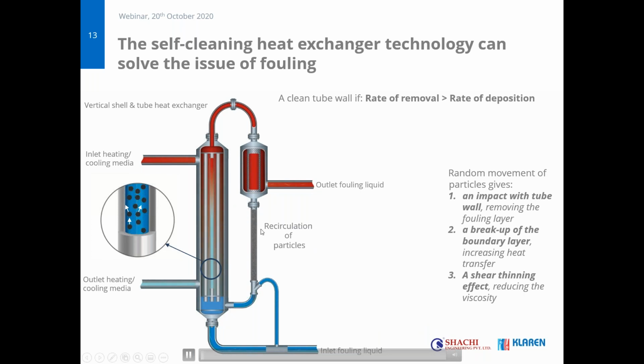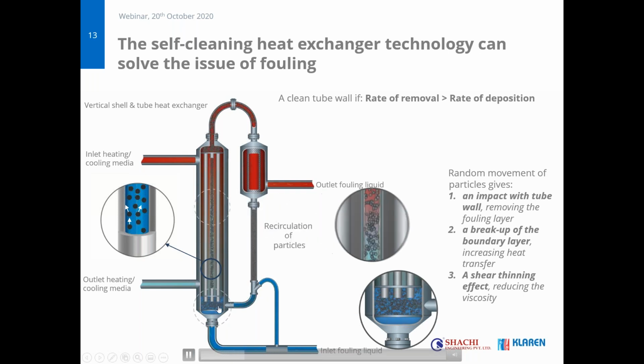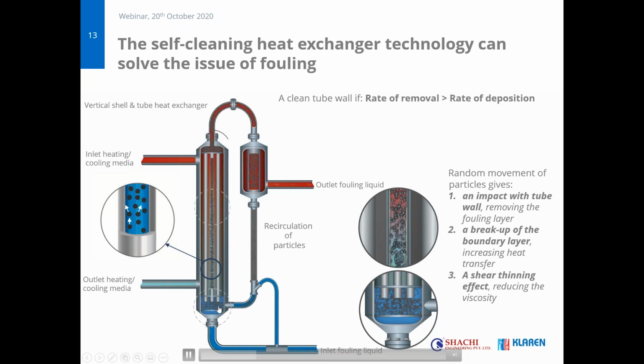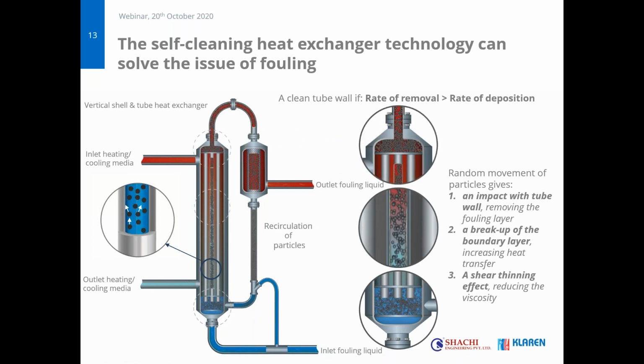But to this loop, we add a loop with cleaning particles, and we supply the cleaning particles from this downcomer into the inlet channel, where the particles are distributed over all the tubes in the heat exchanger. One of the core pieces of know-how that we have is how to design this element such that all tubes experience the same amount of particles, because that is crucial in making sure that all the tubes are cleaned. That might be simple for a heat exchanger that has 3 or 5 tubes, but it's a lot more difficult if you have a heat exchanger with over 400 tubes.